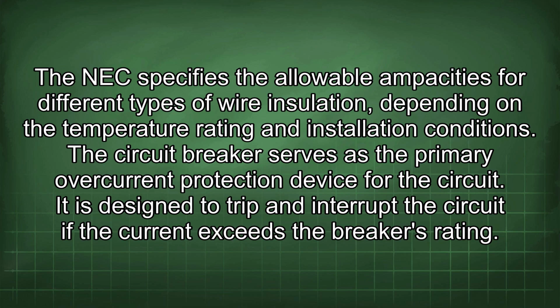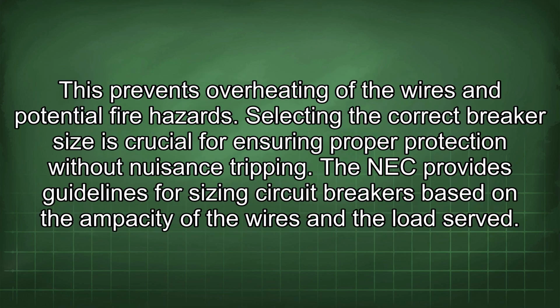The circuit breaker serves as the primary overcurrent protection device for the circuit. It is designed to trip and interrupt the circuit if the current exceeds the breaker's rating. This prevents overheating of the wires and potential fire hazards. Selecting the correct breaker size is crucial for ensuring proper protection without nuisance tripping. The NEC provides guidelines for sizing circuit breakers based on the ampacity of the wires and the load served.